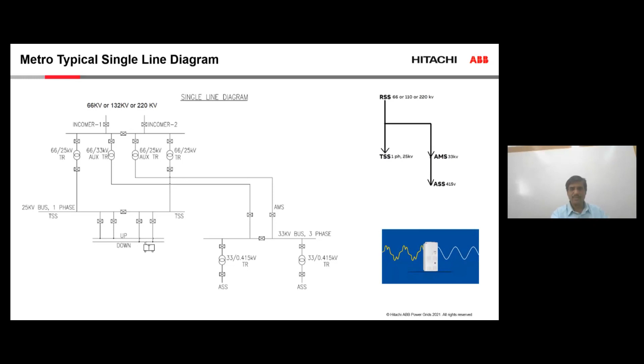So if you look at the power quality issues of the metro, what kind of solutions are we trying to provide here? We are trying to provide a dynamic reactive power compensator that works for both inductive and capacitive load. What does it do? It tries to correct the problem of lagging or leading kVAr. So the first problem at a metro network, on a 25 kV system, is that we have lagging power factor coming from traction and leading power factor from cables. Both lagging and leading kVAr are corrected by a dynamic reactive power compensator, which is very fast in correcting, and it corrects only when it is required. When it is not required, it just stays at zero.